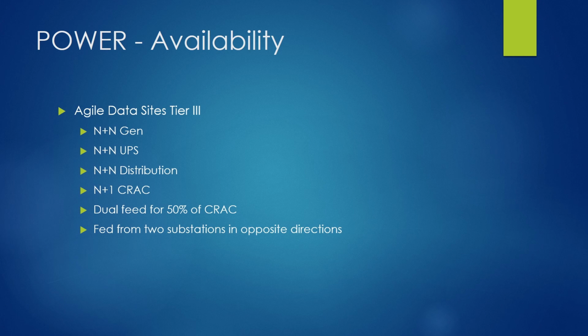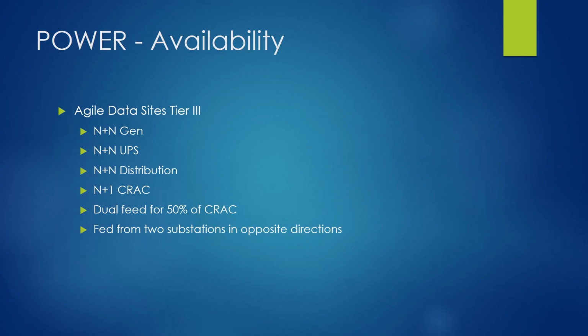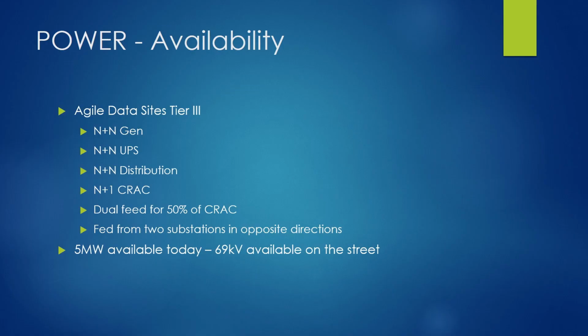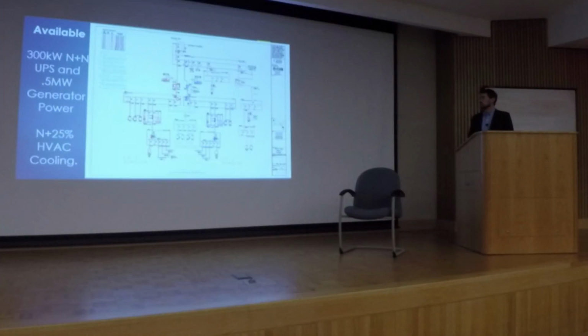We've done computational fluid dynamics models, and we know that will keep us within that ASHRAE TC 9.9 allowable range. Our power is also very highly available from the street because we have 2 substations coming in opposite directions - one about a mile west, the other about 2 miles east. At the moment we have about 5 megawatts here on site. In Allentown we have an ungodly amount of power available, but here we also have a 69 kV circuit available on the street for future use.